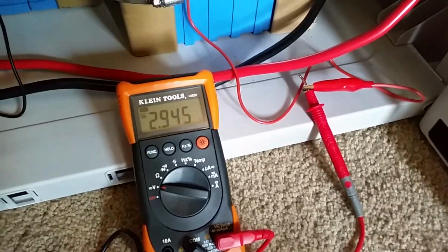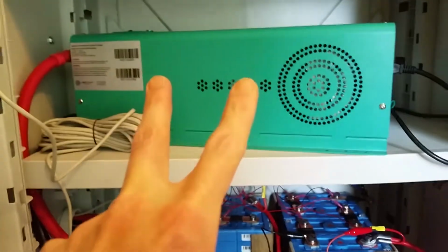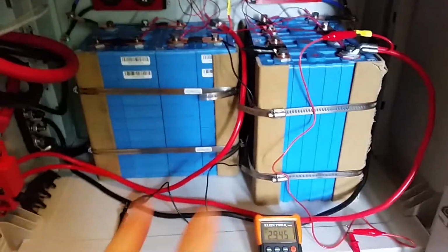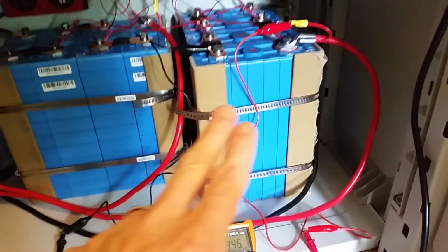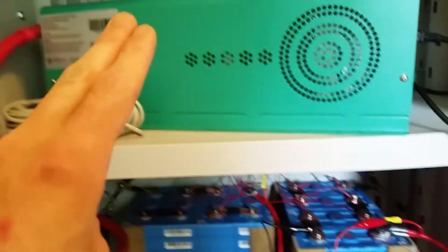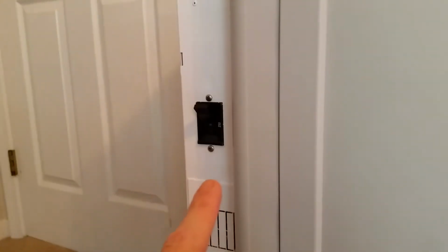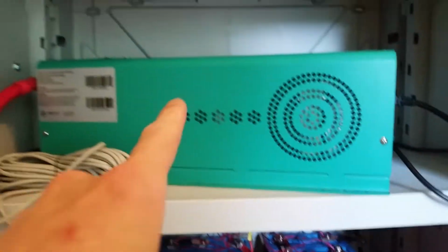And we do have a higher voltage drop across these, from these batteries to the inverter now. Where I got 12.4 at the batteries, we got 12.0 here, so it's about 0.4 difference between the batteries and the stuff in this box, and I'm sure it's more than 0.4 when you measure at the inverter.